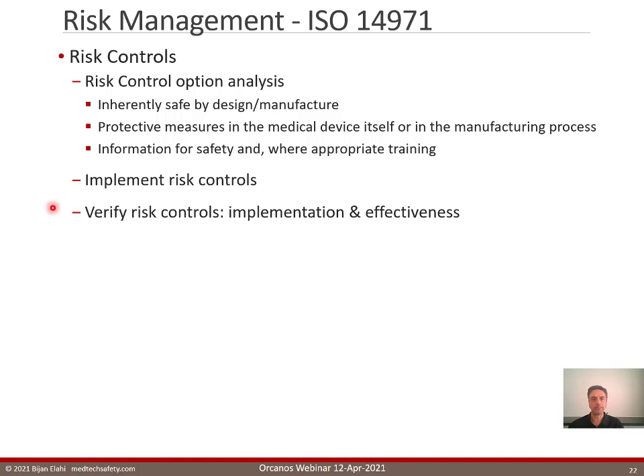And there are two steps in that. One is to verify that we actually did implement the risk control, and the other one is to verify that it's effective. In other words, is the risk control really reducing risk? Do we have any evidence to support that claim? That's what this means. Now we need to look at risks arising from risk control measures. We need to check to see, did our risk control that we implemented cause additional risks, new ones, or exacerbating some of the existing risks? In that case, we need to evaluate and see if we can control those risks, or decide whether the risk control that we did is actually worth it. Maybe it's making things worse.